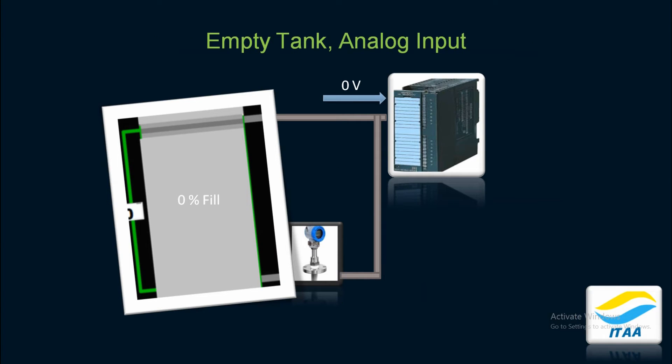Let's look at the foundation. For example, we have an oil tank. If the level of the tank is 0%, the signal going towards the PLC via the transmitter sends standard signals in the form of 0–10V or 4–20mA. Remember, these are standard signals in analog signal processing. When we send a signal from the instrument to the PLC, the signal is normally 4–20mA or 0–10V.